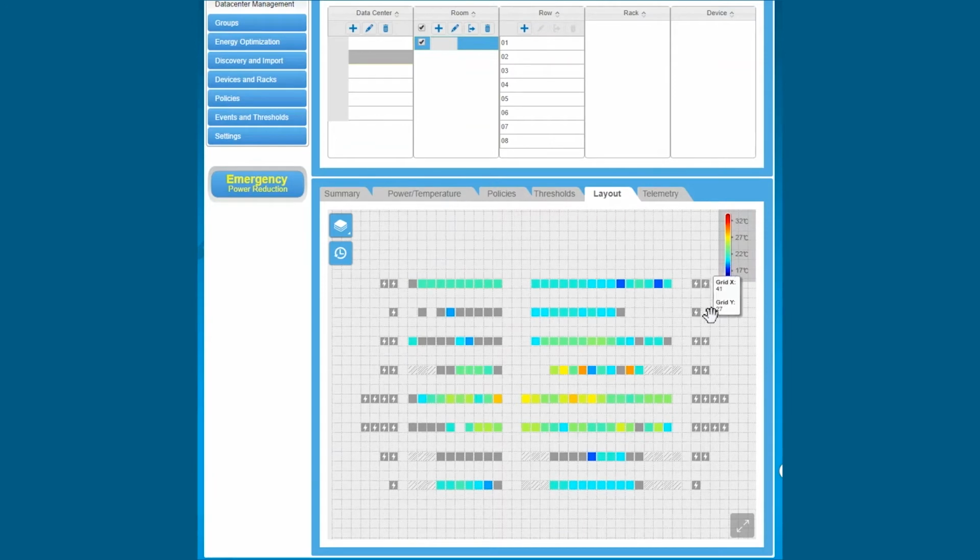So keep in mind, every rack actually has multiple devices in it. So this real-time thermal map is created from the servers inside the rack, and we're actually presenting the average temperature for every rack. So this looks like a very, very healthy data center, right? Because everything is green, maybe bluish. We have just a little bit of yellow over here, but this actually hides the full story.